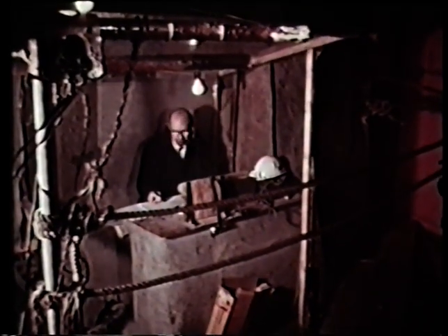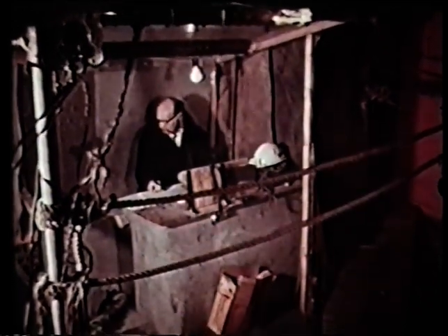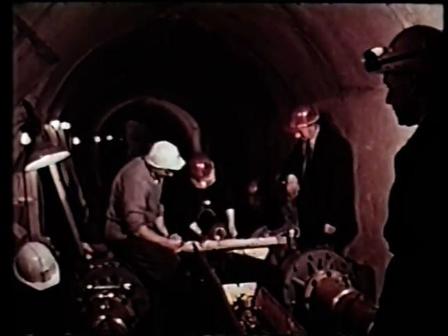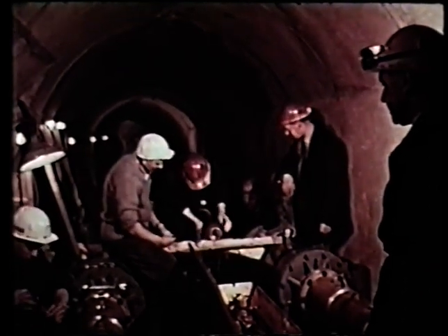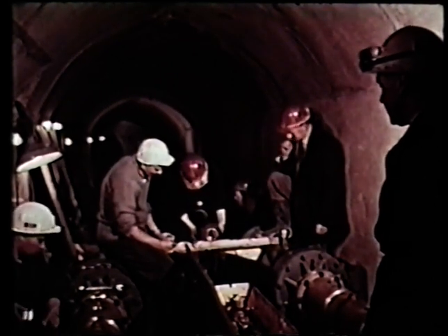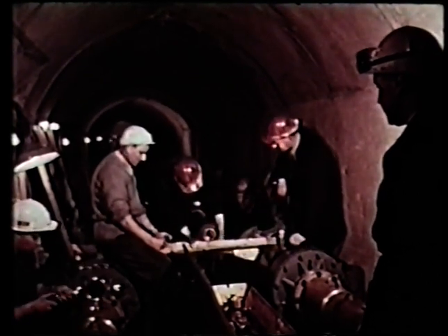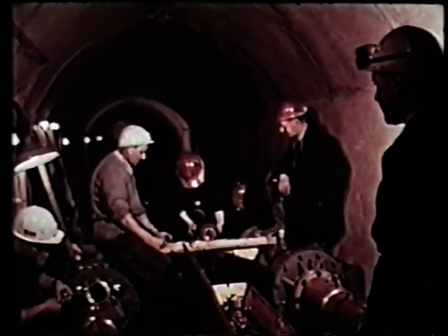The high-voltage oil-filled cables which descend from the outdoor sealing ends at the head of the vertical shaft are fitted wave fashion to wall cleats in groups of three. This provides for longitudinal expansion. Before sealing off the lower termination at the high-pressure stop joints, the cables were partly drained to reduce the hydrostatic pressure. After jointing, the cables were refilled.